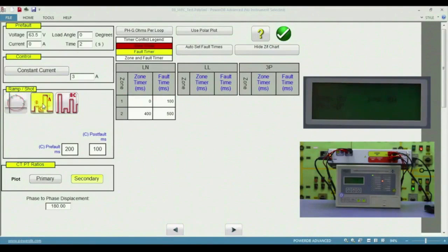In the second option, the linear reach test, we click on a point outside the zone and another point inside the zone. So what the test kit does is, it will inject an impedance outside the zone. Slowly it will reduce the impedance, waiting for the relay to operate, and at a particular impedance, the relay will operate. So this point is identified as the boundary.